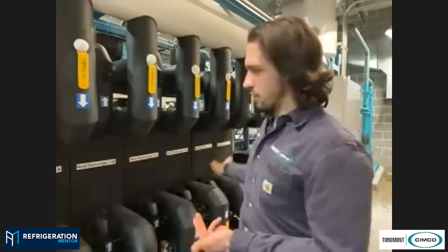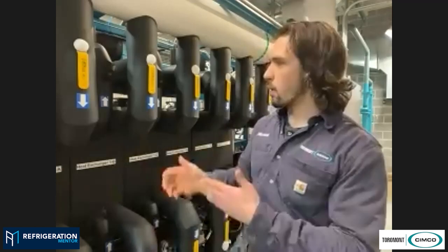Initially, we should cover the three ways that we can control this. We have multiple slab temperature sensors in the concrete measuring slab temperature. We have an IRC camera, an infrared camera measuring the physical surface temperature of the ice. Or we have temperature sensors in our return glycol. But for the most part, we're running this on slab or IRC.